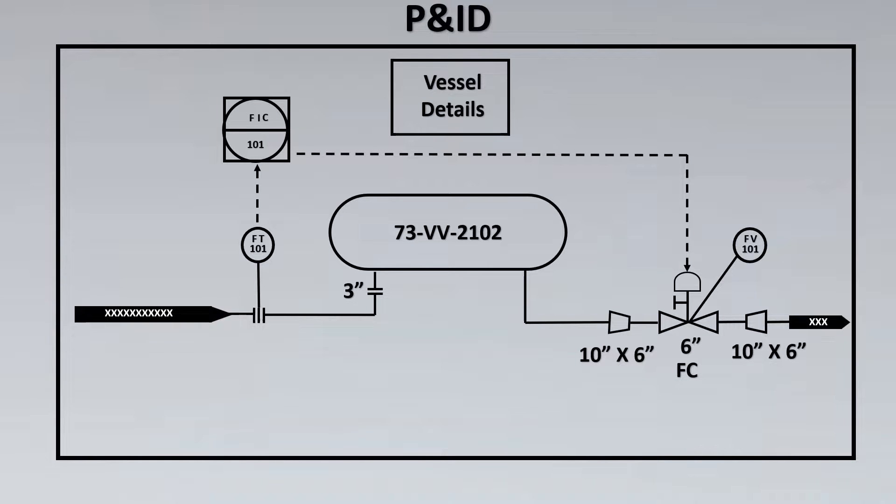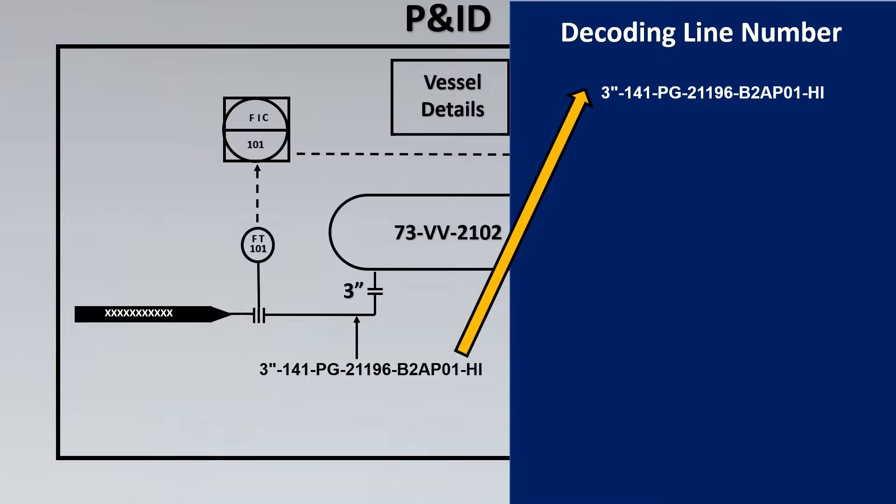Finally once we understand where the line is coming and going from, there's another important thing about a line which needs to be known. What is that? That is nothing but the line number. This is extremely important for almost any engineer that is working in any P&IDs. So let's try to decode and understand the line numbers. So first thing here is the first thing stands for the line size. So what is your line size? Is it 3 inch, 4 inch, you get to know that.